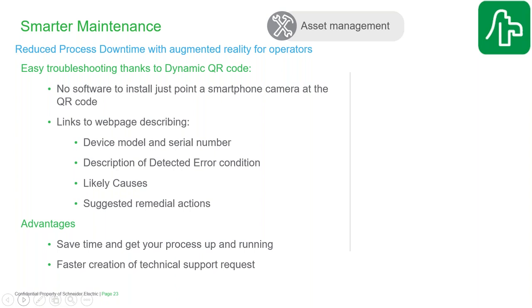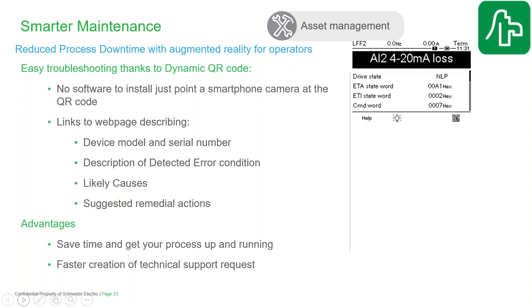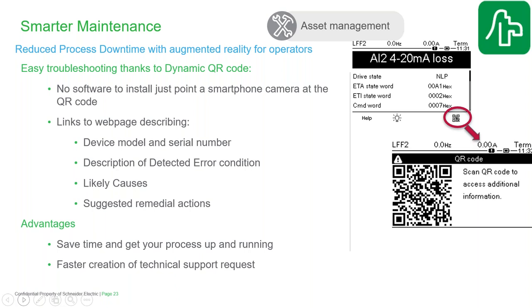In addition, if problems do occur, and inevitably problems will occur, that's just life, how do we ensure that we get things running again as quickly as possible? One example of this with the Altivar Process drives is that the built-in diagnostic capabilities will detect many error conditions, and the screen, like you see there, will come up with an error message telling you what it is. But one thing on there is that little icon in the corner. If you press the keypad button just below that, it will change the screen and bring up a QR code.